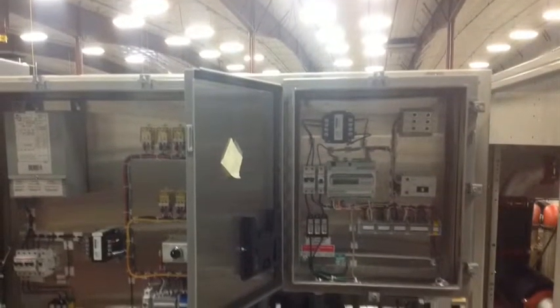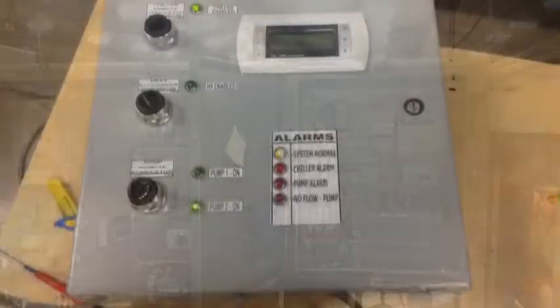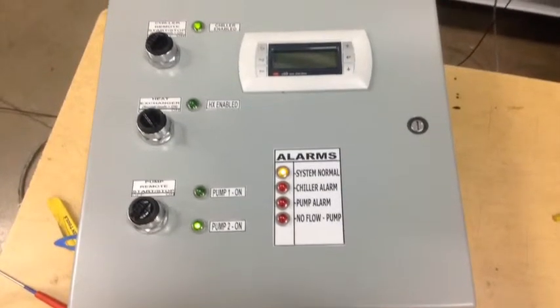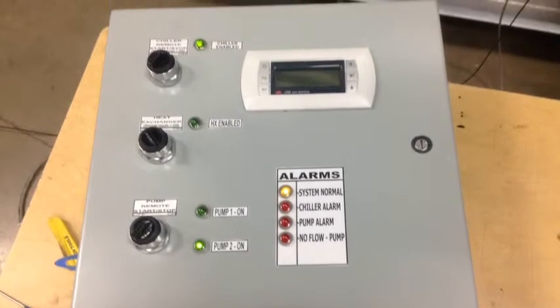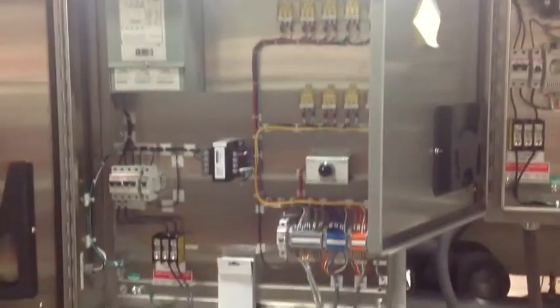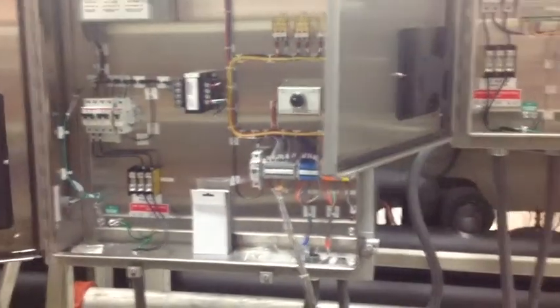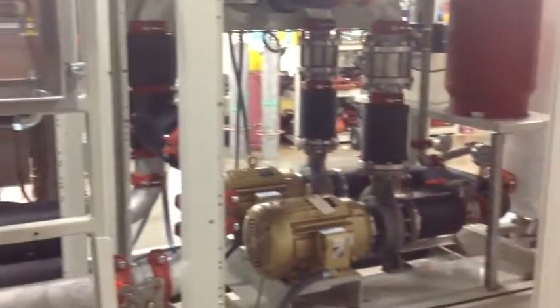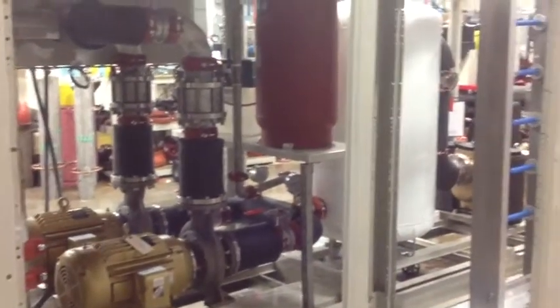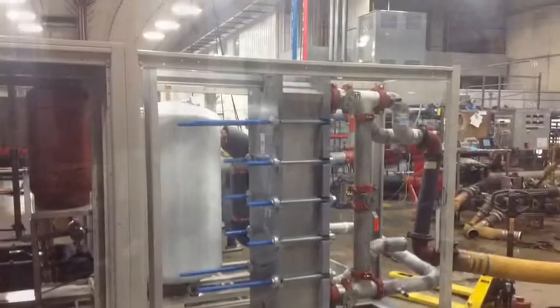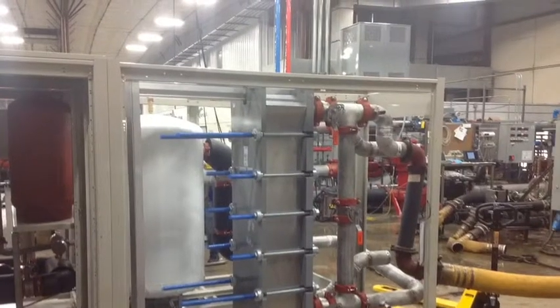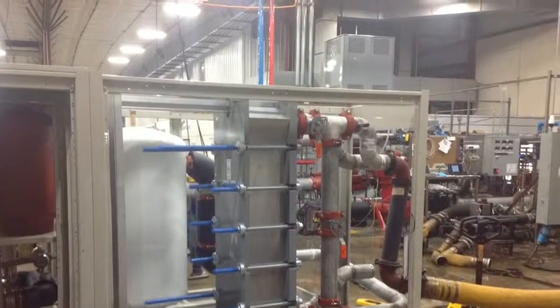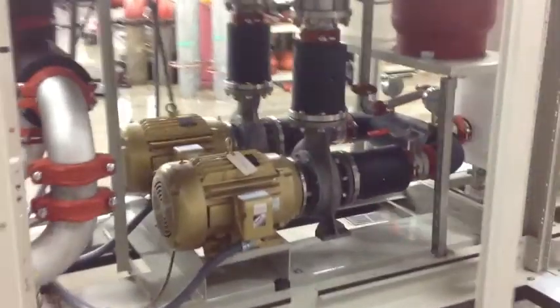These 2 panels are the C1 box on the left, which interfaces to this remote panel. The other panel was a control panel for the heat exchanger and control valves. Back looking down at the C1 panel, now panning to the heat exchanger control panel, and then back to the right, now on the back side of the auxiliary modules, showing the chilled water pumps, expansion tank, glycol mini feeder, and now the plate and frame heat exchanger and the storage tank.